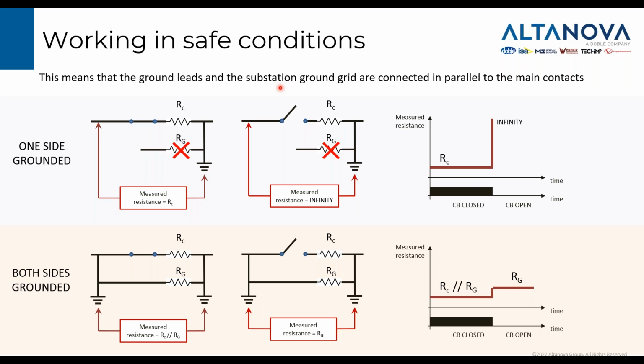But if you are using the standard method, one of the two grounds must be removed, because if you remember from the beginning of the presentation, the way to perform the measurement is to check if the resistance is going from a very low value to infinity. But if you have the two sides grounded, this is not true. You are going from a low value of resistance to another value that is not for sure infinite, and maybe extremely low. So this delta can be low, and I need a device able to detect this small delta. And for sure, the standard method doesn't guarantee accuracy in such a condition.